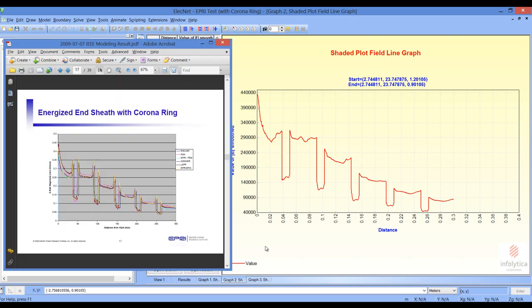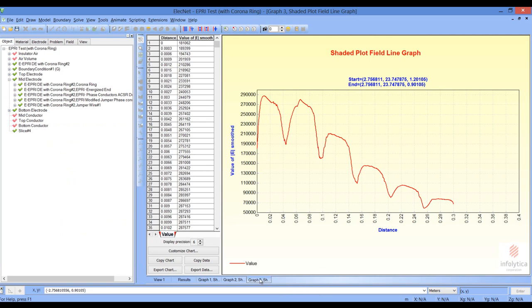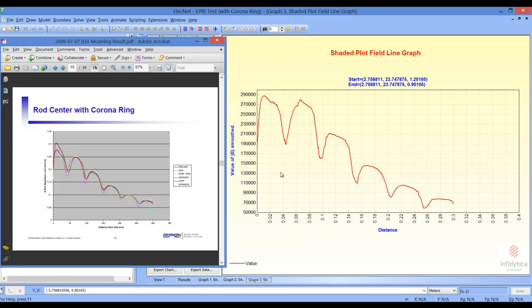Again, we can compare this to the results from the EPRI report. Finally, we want to look at the contour along the rod center. The results from that contour show that the field is very much reduced in the rod center due to the presence of the corona ring. Again, we want to compare that to the results from the EPRI report.